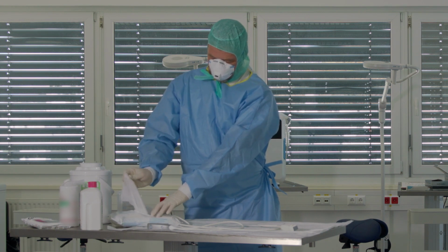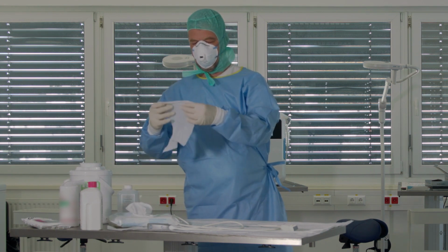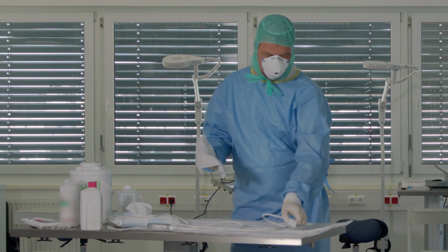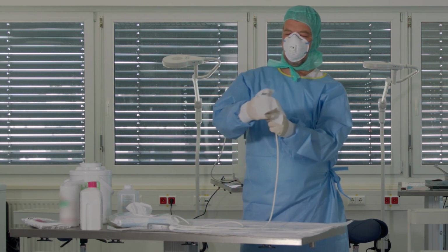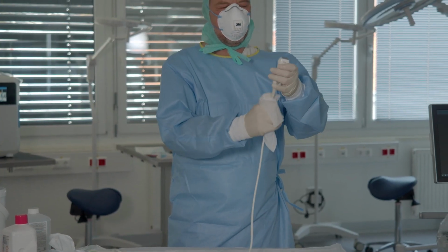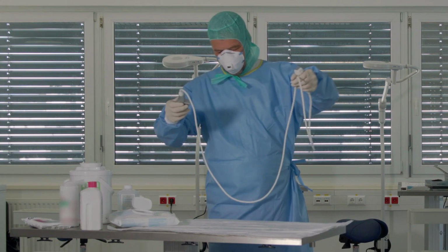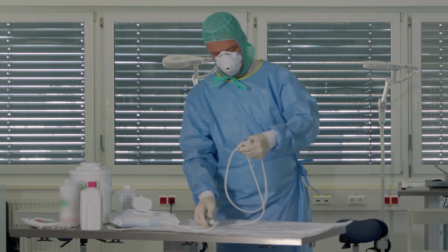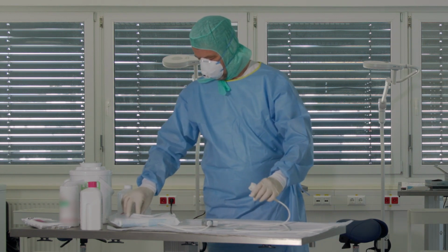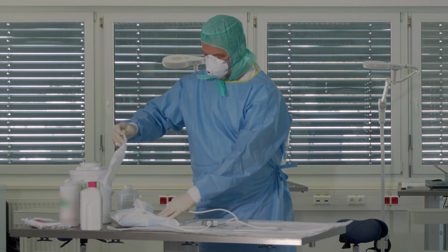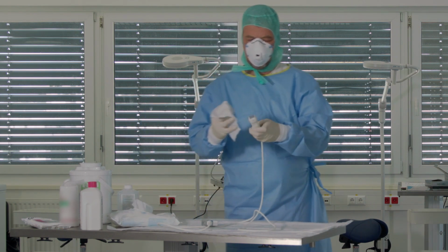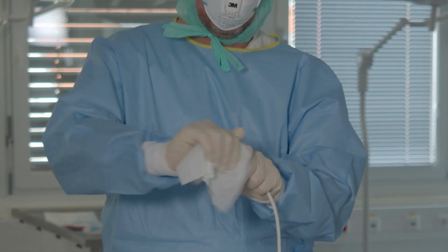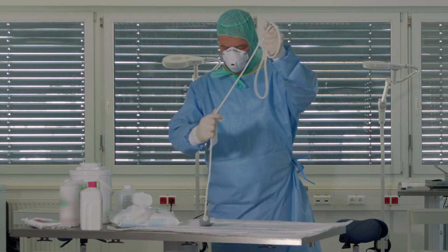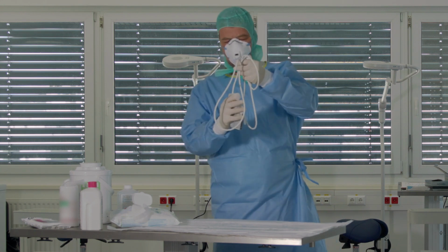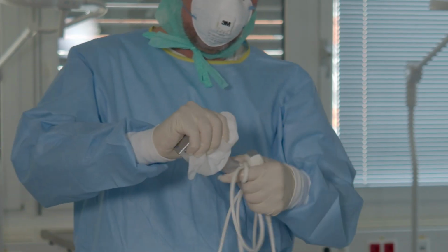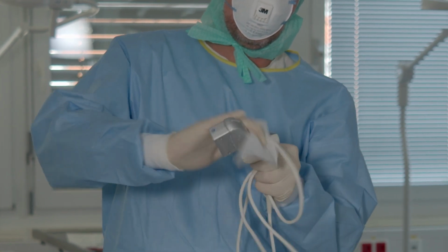Proceed to cleaning the transducer. Be sure to remove all visible debris and clean all parts of the transducer, including the cable and connector. Finally, disinfect the transducer again and finish off by wiping its cable as well. Replace with a new wipe if dry. When cleaning the connector, be careful not to damage the pins.